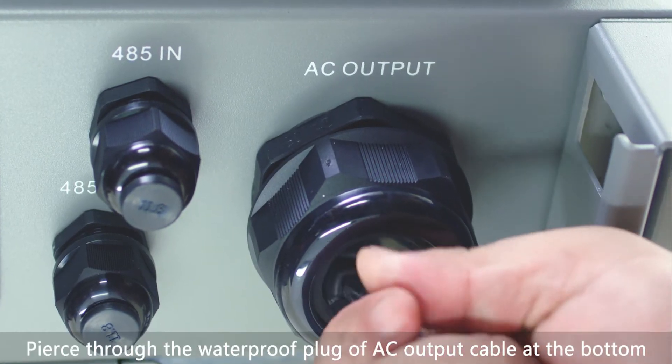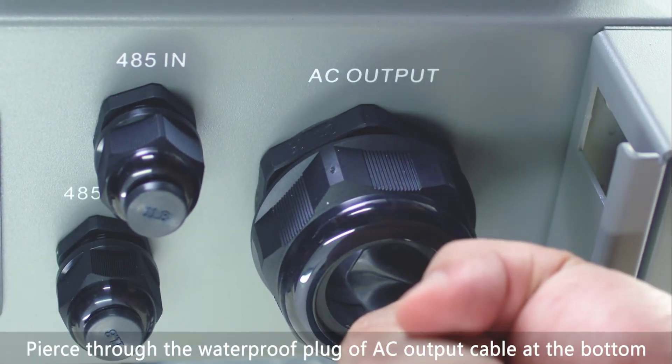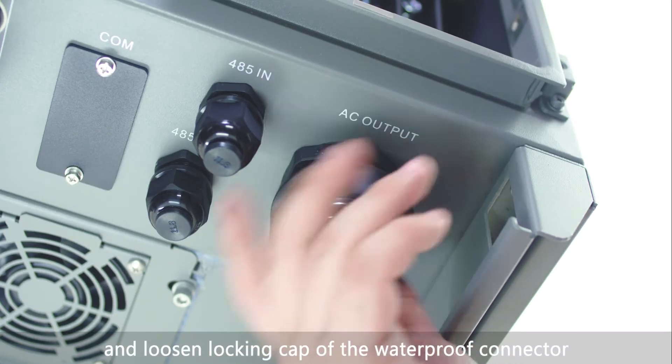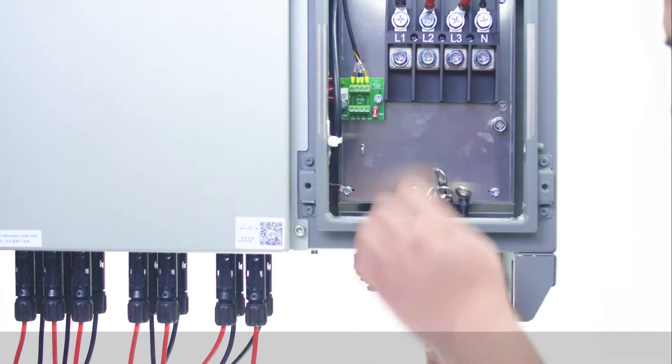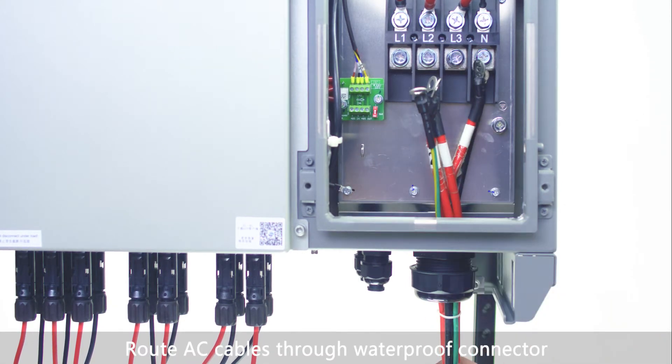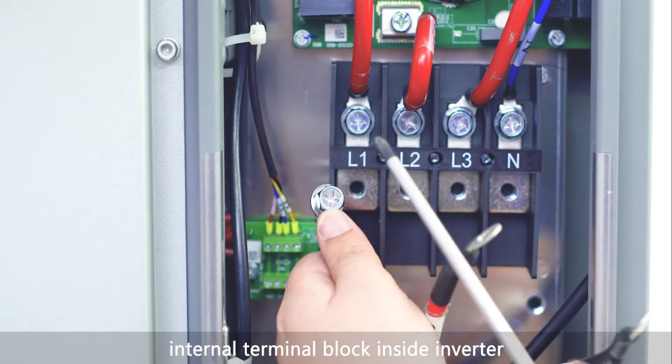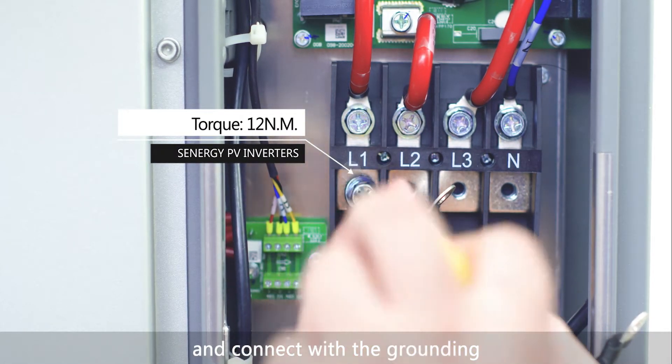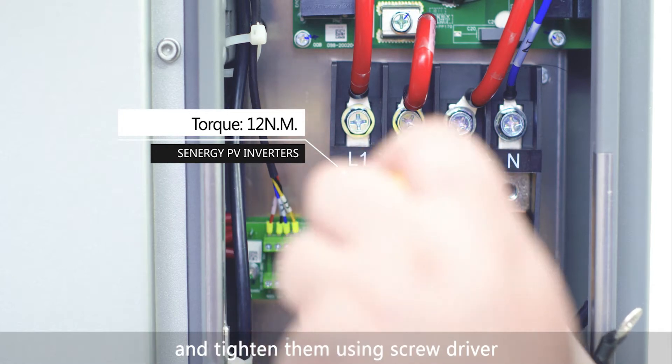Pierce through the waterproof plug of AC output cable at the bottom of inverter using edge tool and loosen locking cap of the waterproof connector. Route AC cables through waterproof connector. Connect the AC cable to the internal terminal block inside inverter and connect with the grounding, and tighten them using screwdriver.